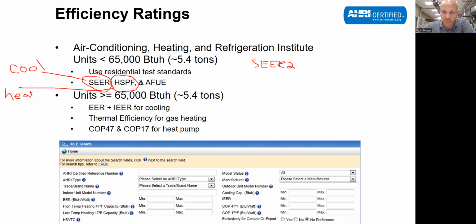I believe we briefly talked about this on Friday. The old testing standard was changed for the static pressure in the ductwork that we have to test all this stuff at. So now there's a new standard. So SEER 2 and HSPF 2. You will also see EER or EER2 for all that size equipment, right? EER2 being the new one.